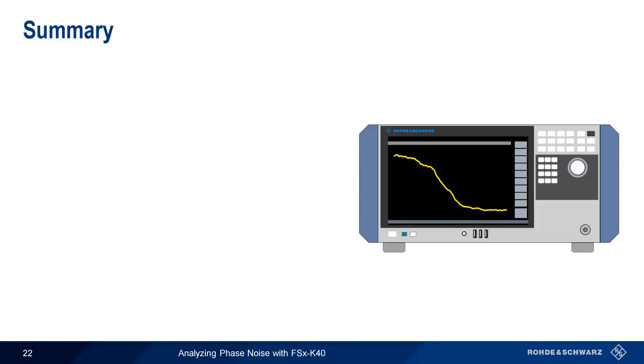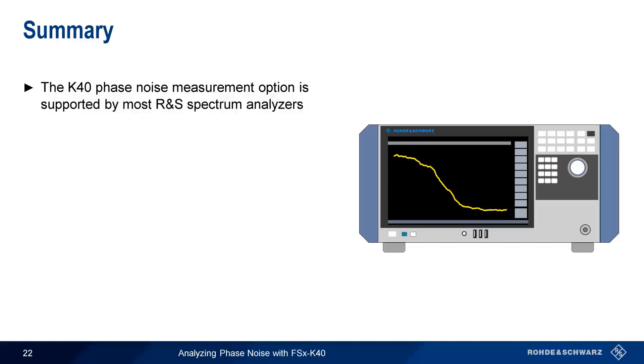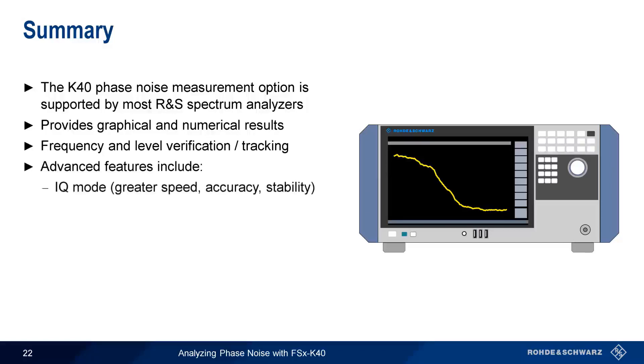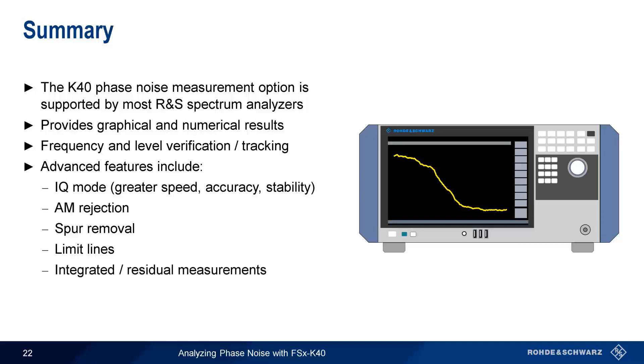In summary, the K40 phase noise measurement option is supported on most Rohde & Schwarz spectrum analyzers and enables user-configurable automated phase noise measurements. It provides standard single sideband graphical results as well as numerical results. The frequency and level verification and tracking function is very helpful when measuring drifting or unstable sources. Advanced features based on IQ data offer higher speed, better accuracy, and AM noise removal. Tools such as spur removal and limit lines aid in analysis, and the K40 option automatically calculates integrated or residual measurements of phase noise. This concludes our presentation, Analyzing Phase Noise with FSx-K40.